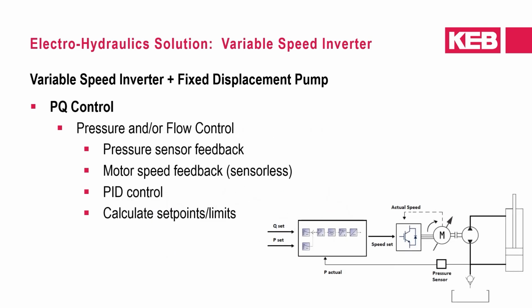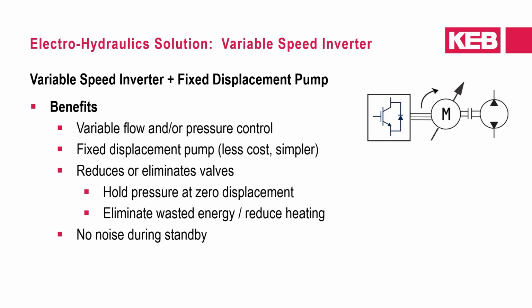Inverter control of the pump allows for pressure and/or flow control. The control concept uses feedback from a pressure sensor and the motor speed, which can be sensorless, in PID loops to calculate the output motor speed and torque needed to regulate the set pressure and flow commands. With this type of solution, you can get the benefits of both pump types.